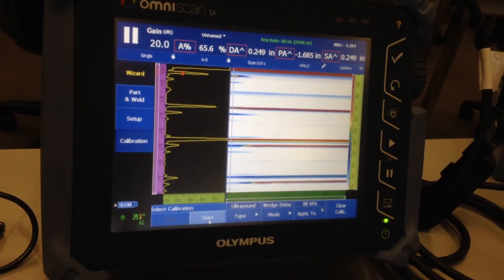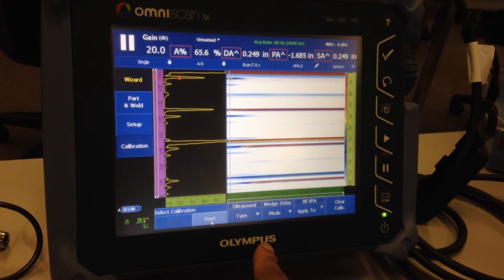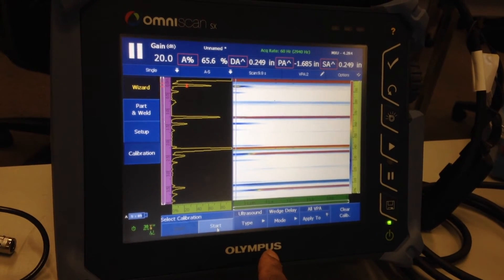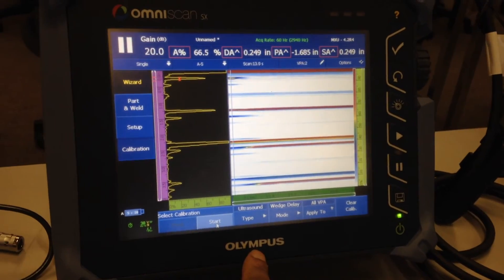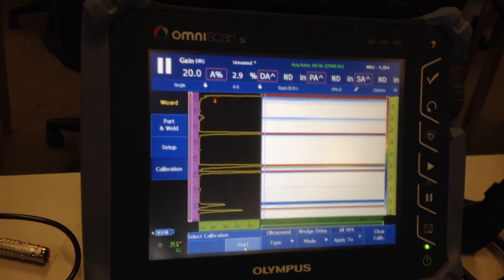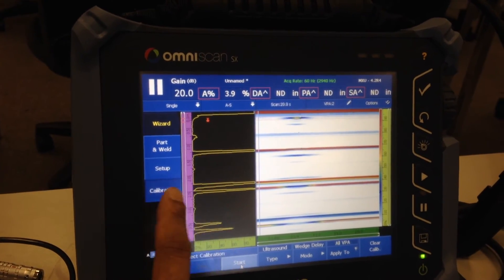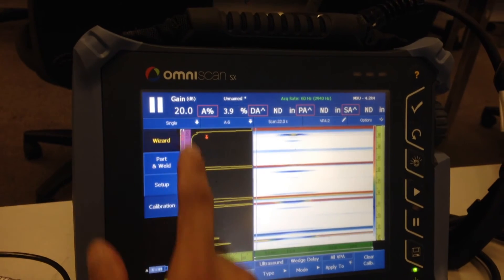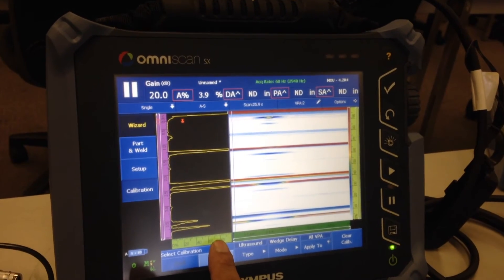The next thing I want to do is a sensitivity calibration. Now for a sensitivity calibration, it just depends on the type of inspection you're going to do in the field, but in this case let's just practice a sample sensitivity setting. So in this case I'm going to play with my gain and get my second back wall to 80% screen height.